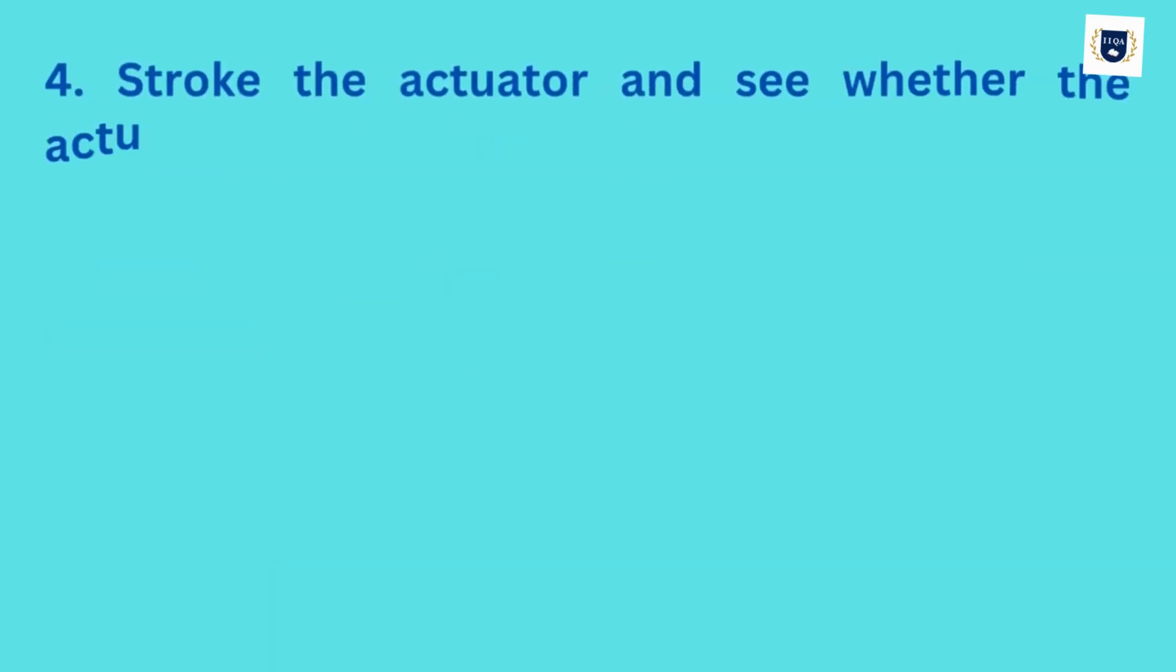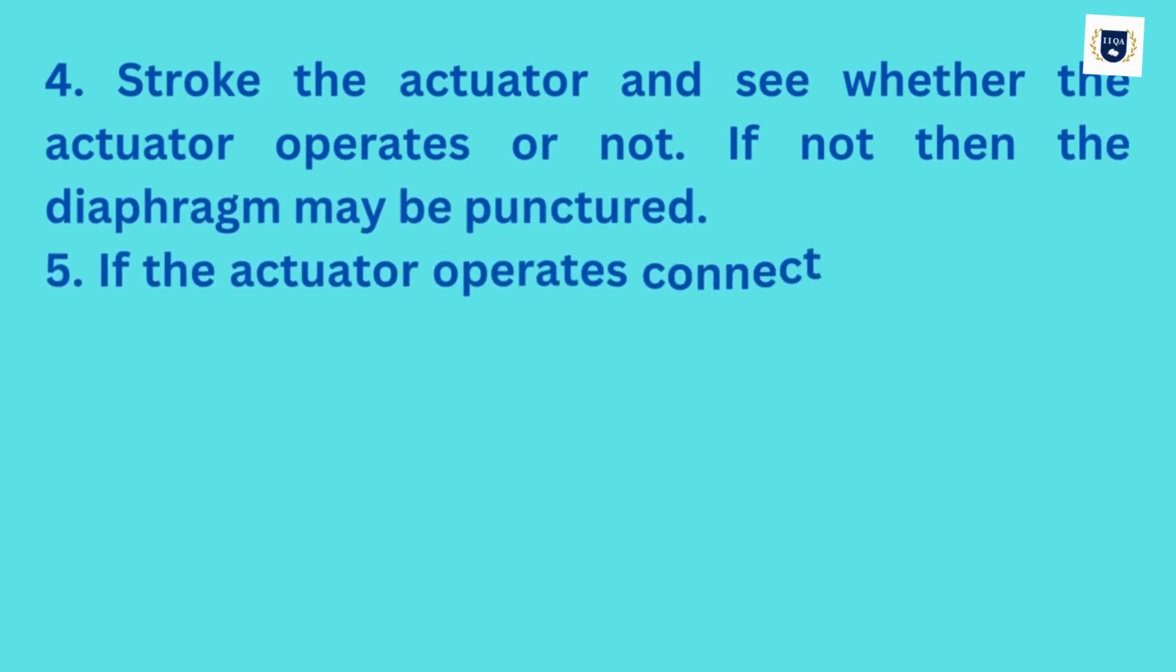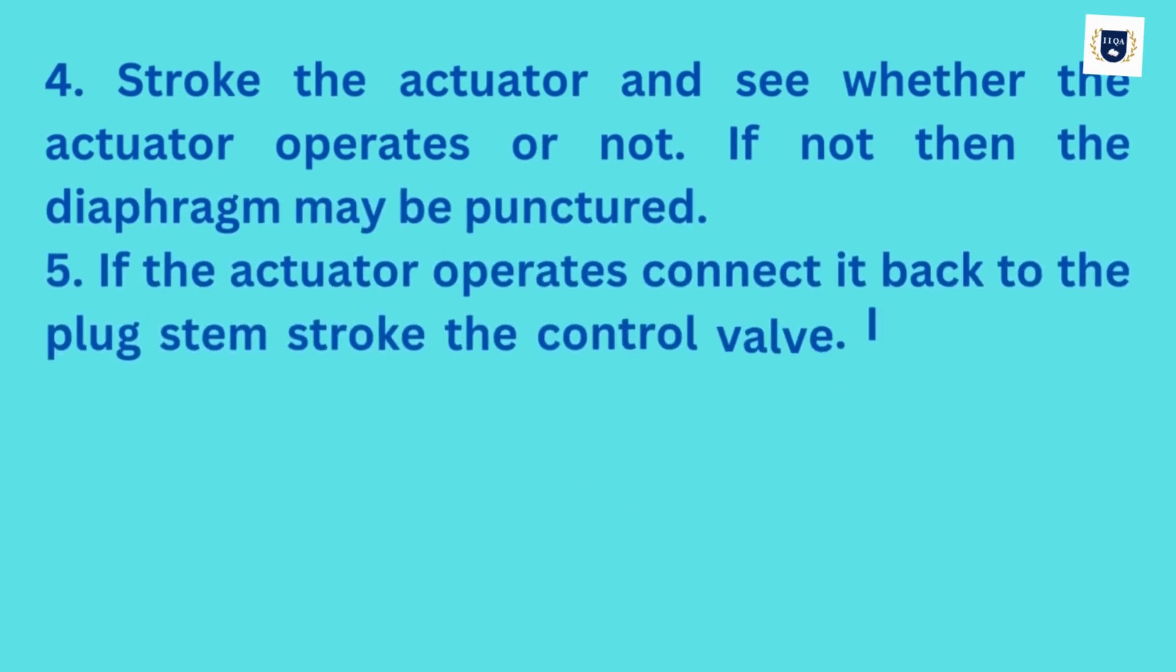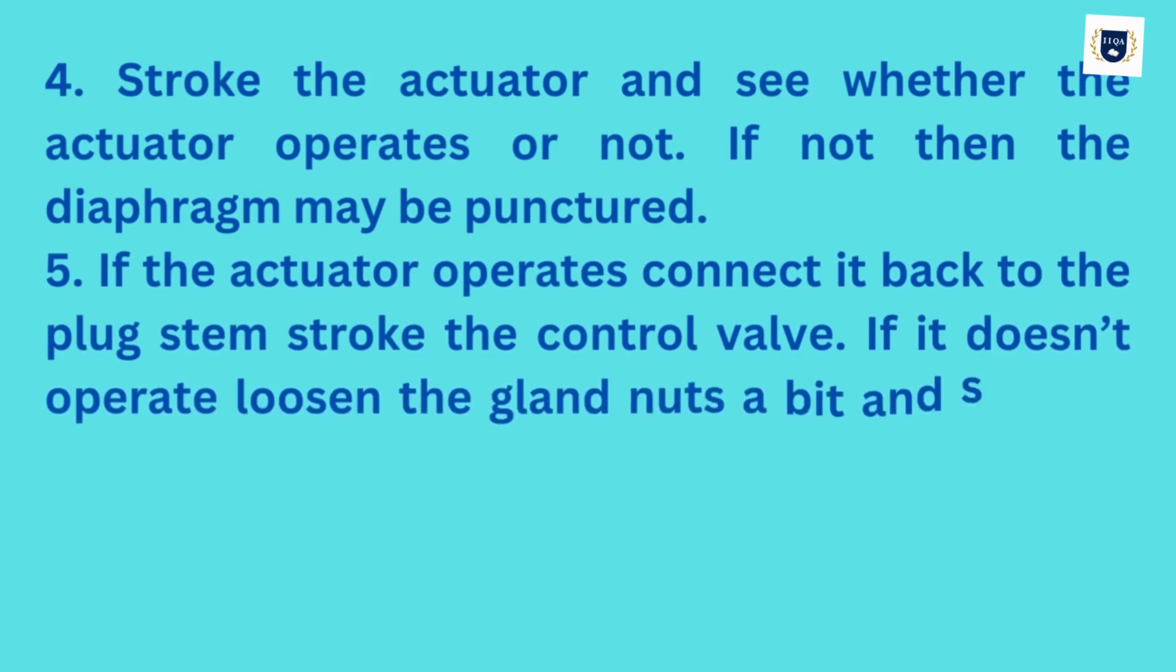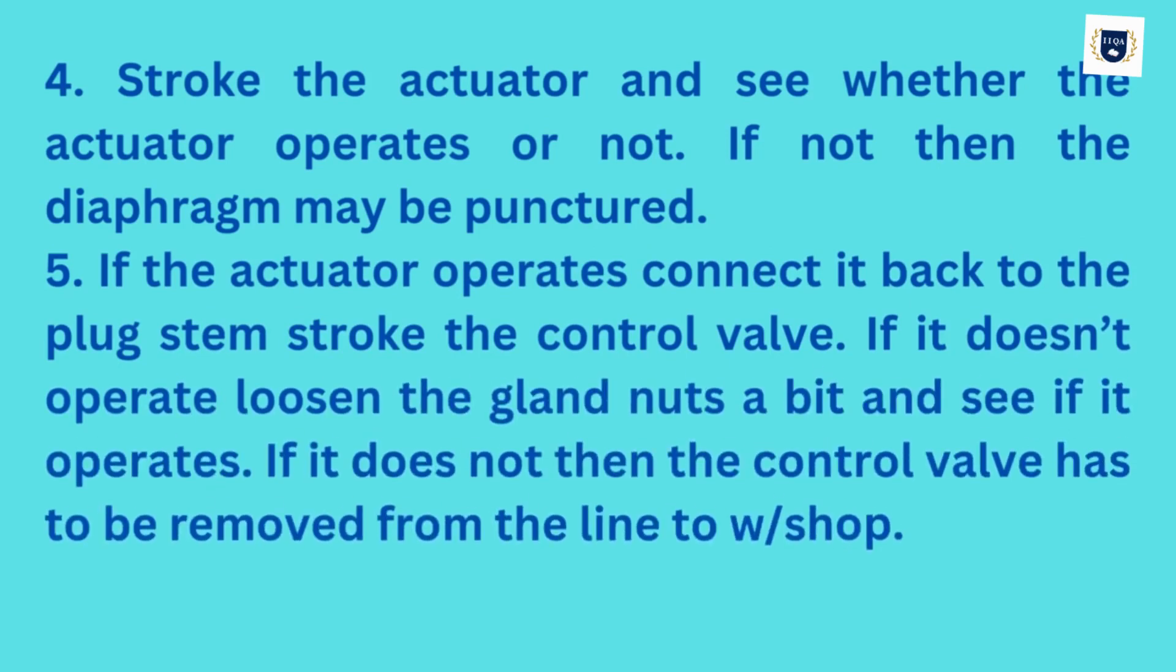Stroke the actuator and see whether the actuator operates or not. If not, then the diaphragm may be punctured. If the actuator operates, connect it back to the plug stem and stroke the control valve. If it doesn't operate, loosen the gland nuts a bit and see if it operates. If it does not, then the control valve has to be removed from the line to the workshop.